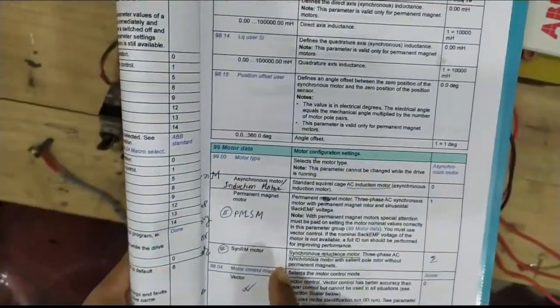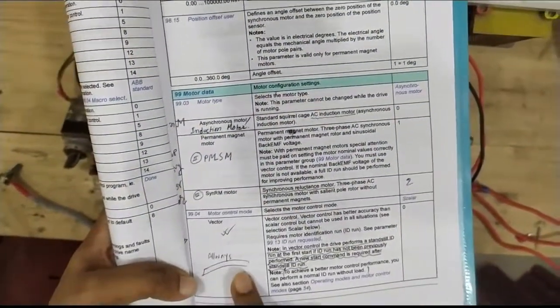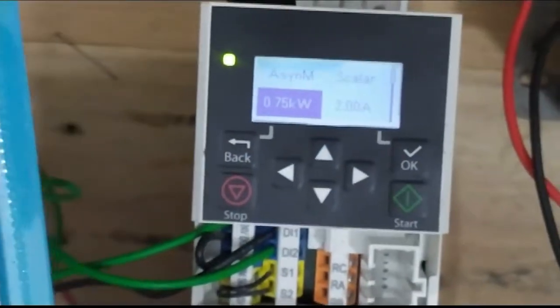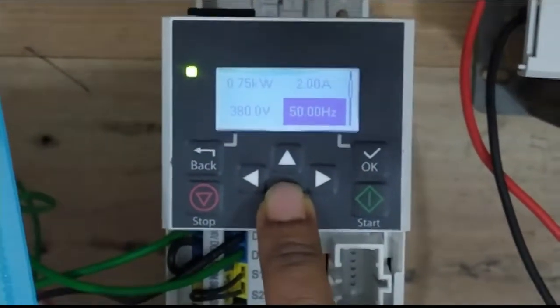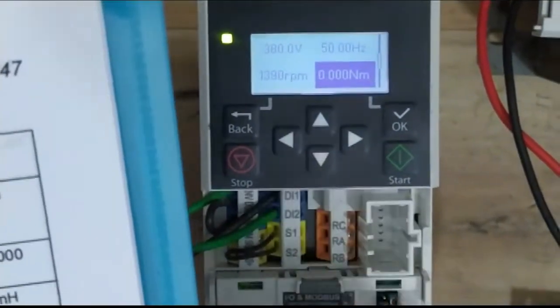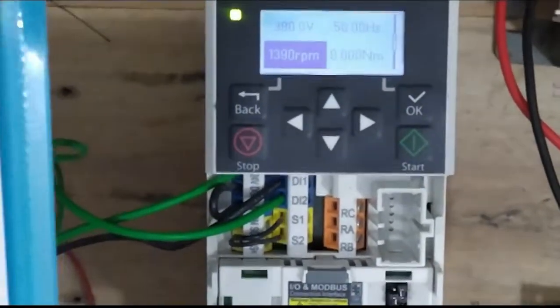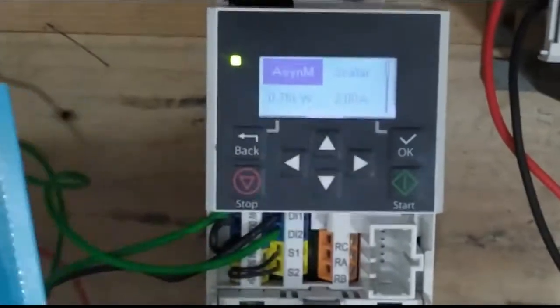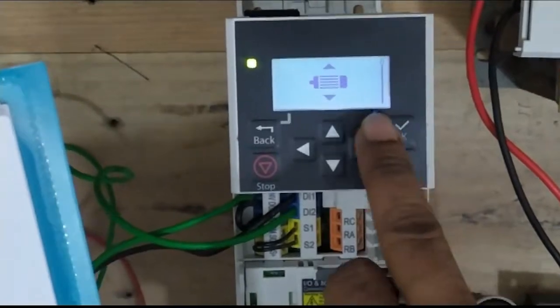An asynchronous motor is like an induction motor — it runs asynchronously. We selected asynchronous motor because it's a normally used induction motor. The rating is 0.75 kilowatt, 2 amperes, 380V, 50Hz — all selected from the motor nameplate. That's why we selected the same kinds of parameters in our VFD, introducing our induction motor through the 99-parameter group.